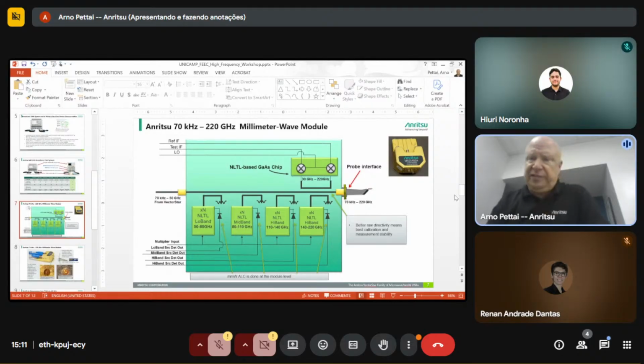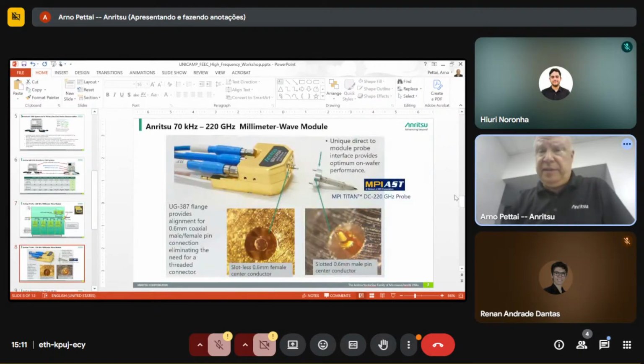Because it goes to 220, we had to, of course, innovate what would be the interface for that. When we're looking at 110 and 125, we're working with a 1 millimeter coaxial connector. When we're looking at 145, we're working with a 0.8 millimeter connector. But for the case of the 220, we had to take it a step further. And so here what we have is an interconnect scheme that uses the 0.6 male-female pin arrangement, where the female side is on the module interface, and whatever we connect to that interface would be a male pin. So in most cases, that would be the probe. That's where we're going to be actually calibrating and making our measurements across the full 220 gigahertz broadband range.